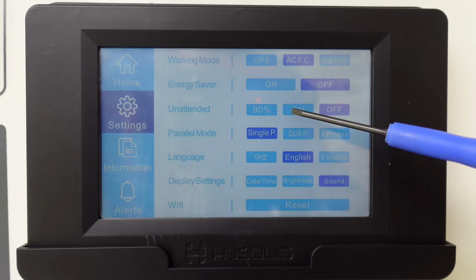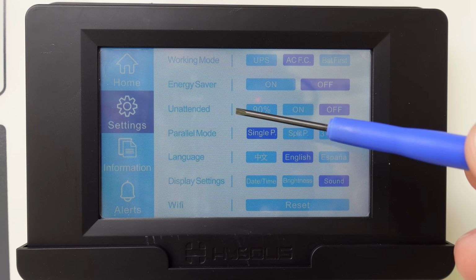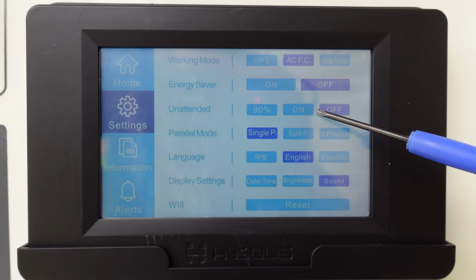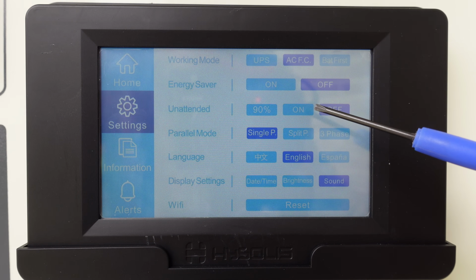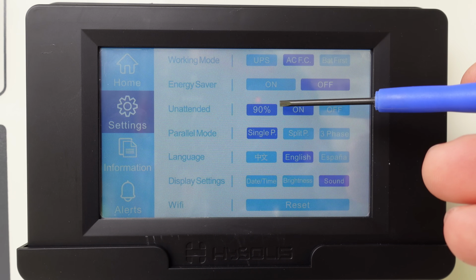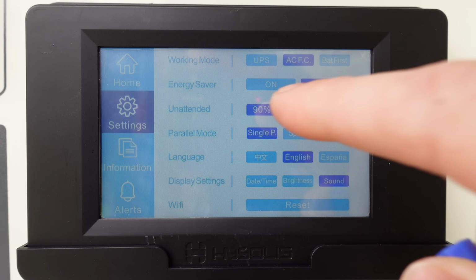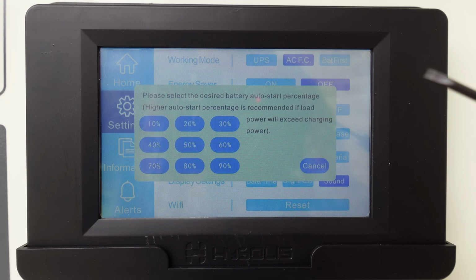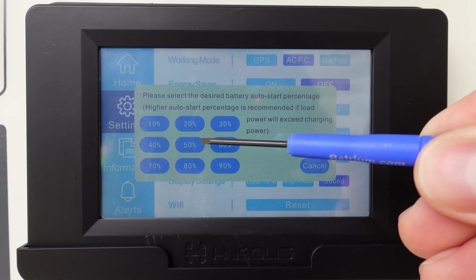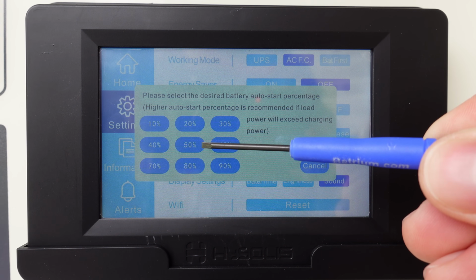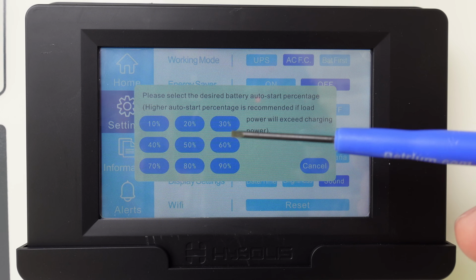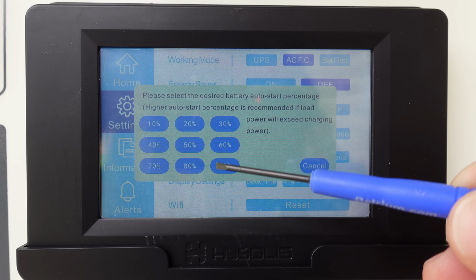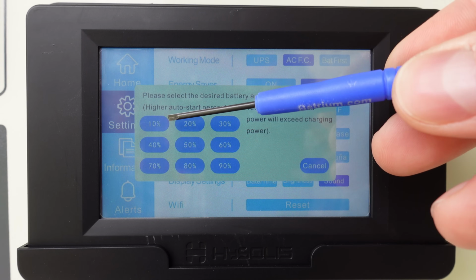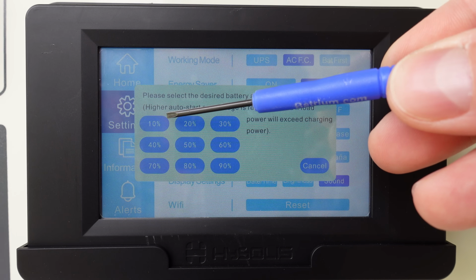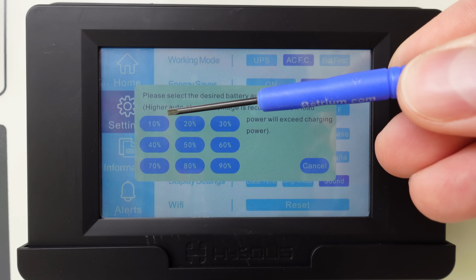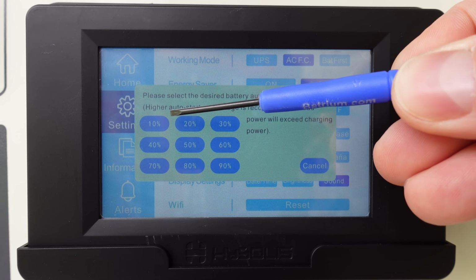We have unattended mode, and this is an interesting new feature. Unattended mode will allow the inverter to turn back on automatically once solar power is available and begins charging the battery. And then you'll also need to set the state of charge percentage for which the inverter should turn back on. So it's defaulted to 90% here. So let's say we select 50%. This will allow the solar to charge the battery up to 50% before it turns that inverter back on. If you have a larger load connected, you'll want to select a higher percentage. You wouldn't want to set this for, say, 10% if your solar does not meet the demands of both the charger and the connected loads. That's going to result in frequent cycling of your inverter, and you want to avoid that.